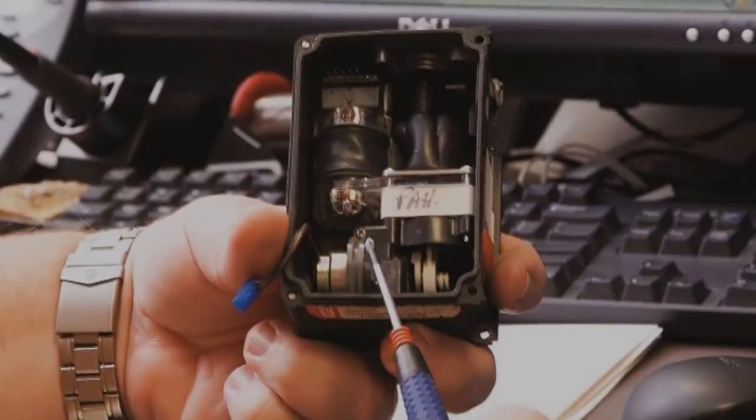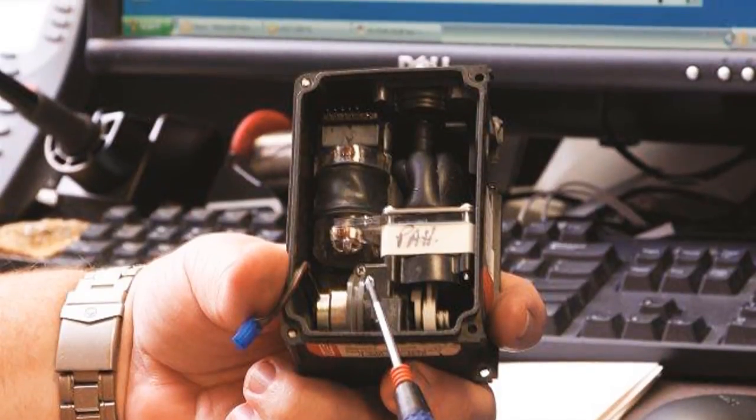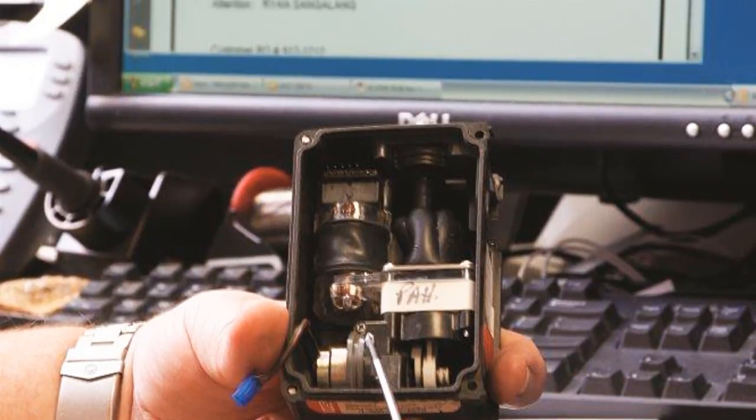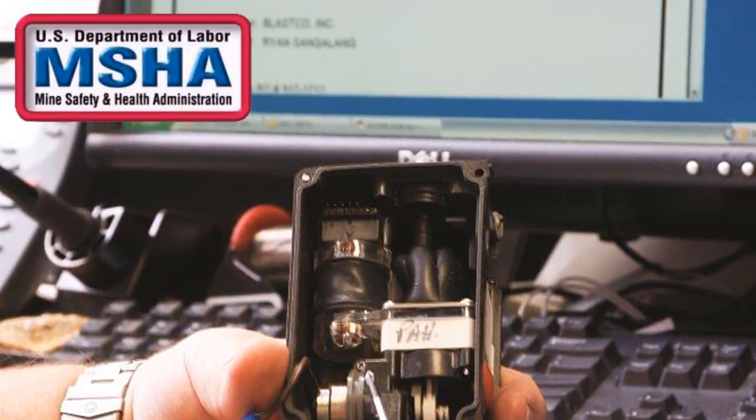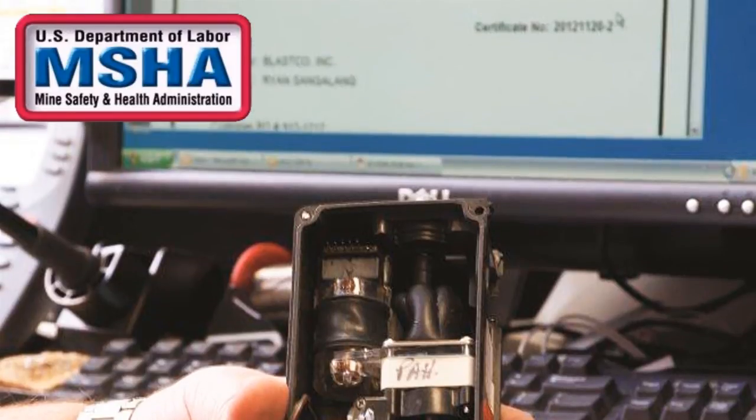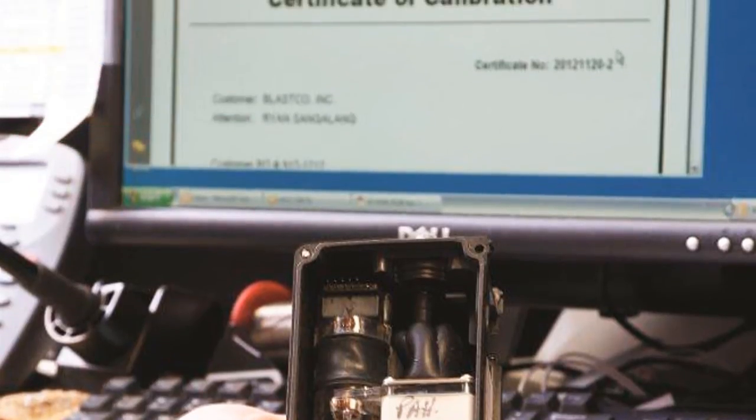Any repair work for Escort pumps that are to be used in underground coal mining must be performed by an MSHA certified technician. Failure to do this will result in a pump that is non-compliant.